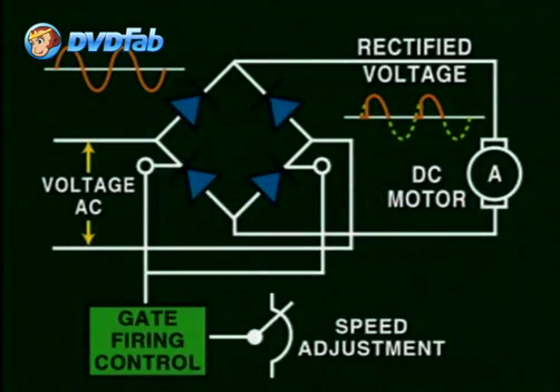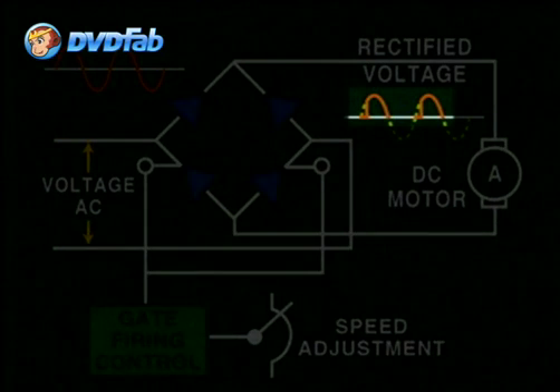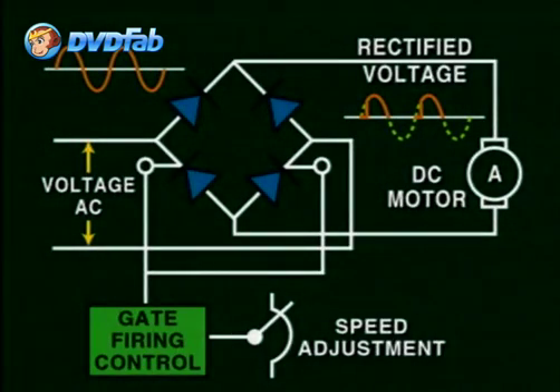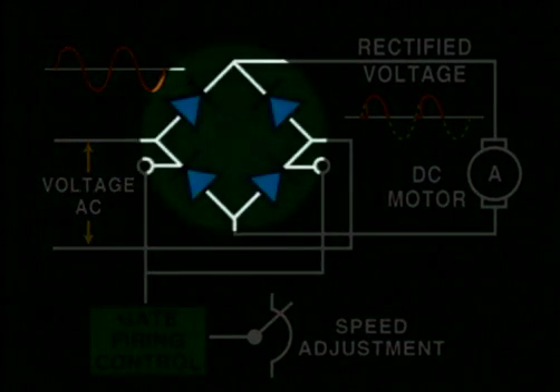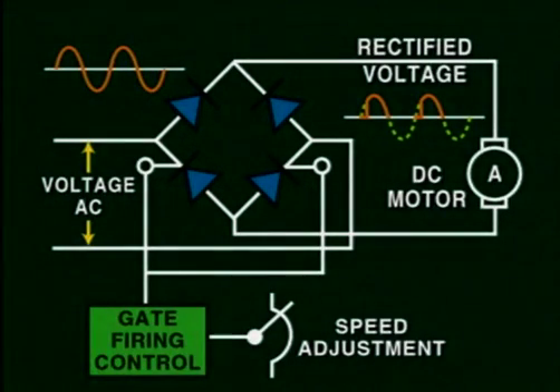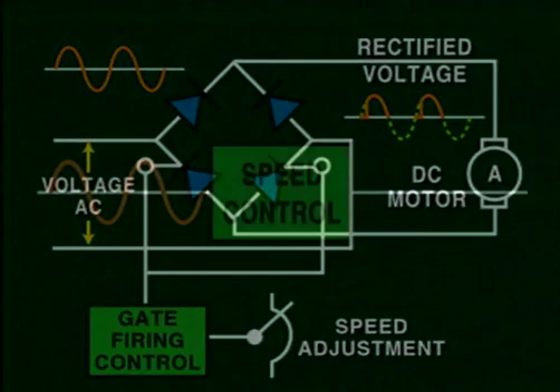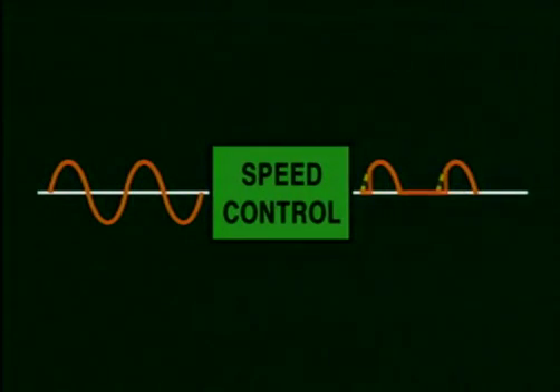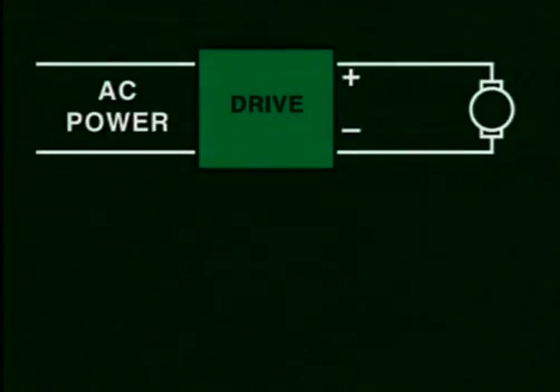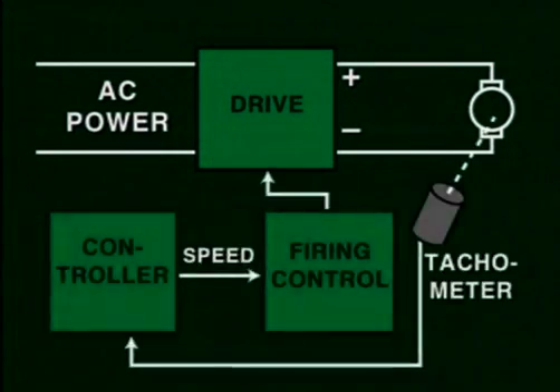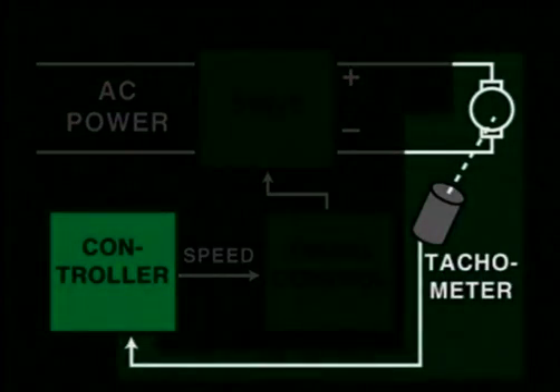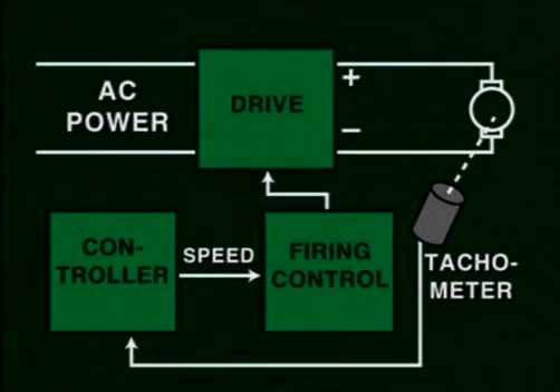When used in a bridge rectification circuit, the SCR will vary the amount of DC output voltage. This circuit forms part of a solid-state speed control. As you can see, the power source for the motor is AC, which is being rectified by the bridge in the speed controller and at the same time controls the amount of applied voltage to the motor. As the SCR is fired faster, the voltage will increase, while if it is fired slowly, the voltage will be reduced. These drive systems are usually used in what's known as a closed loop, where a feedback signal, such as from a tachometer, is fed back to a controller, such as a programmable controller, which makes the necessary adjustments to the drive's firing circuit to keep the speed constant if there are any load fluctuations.